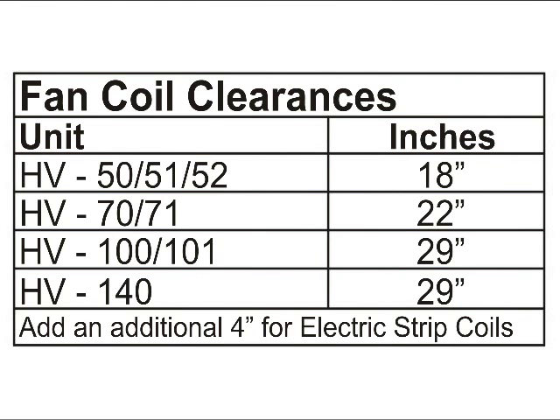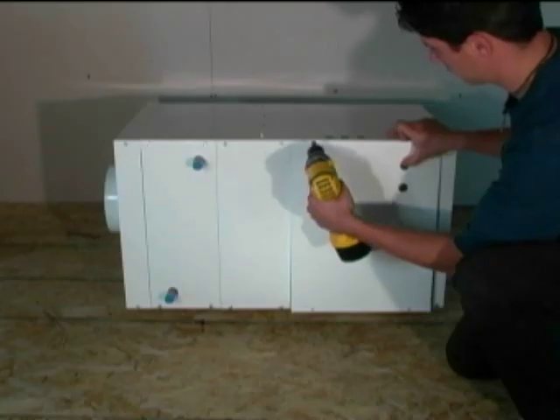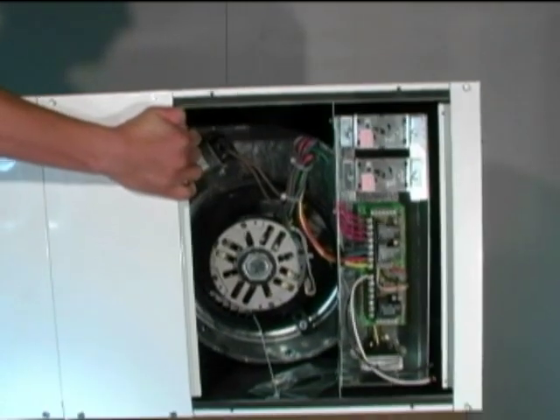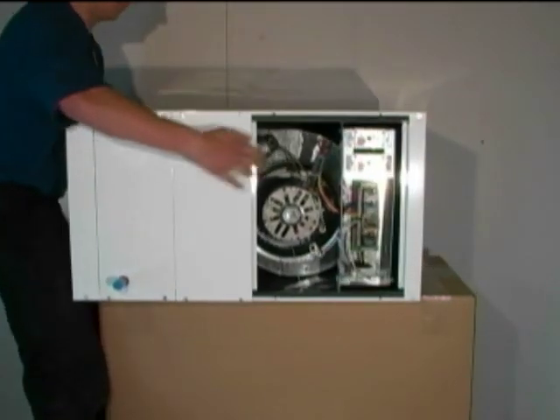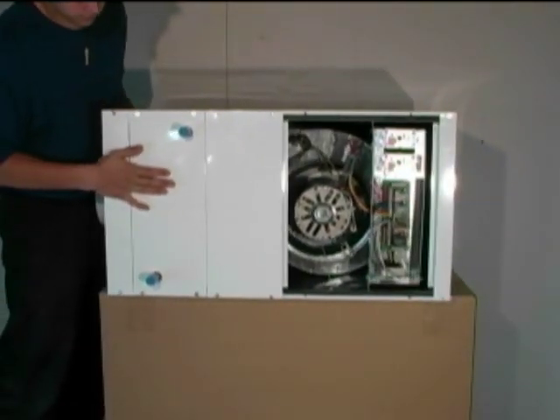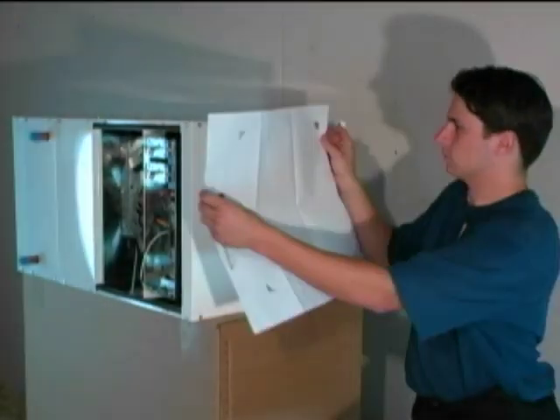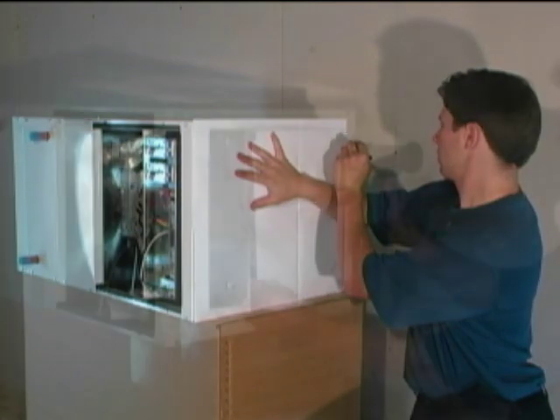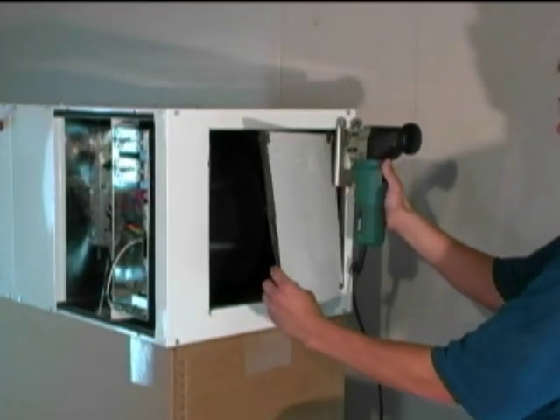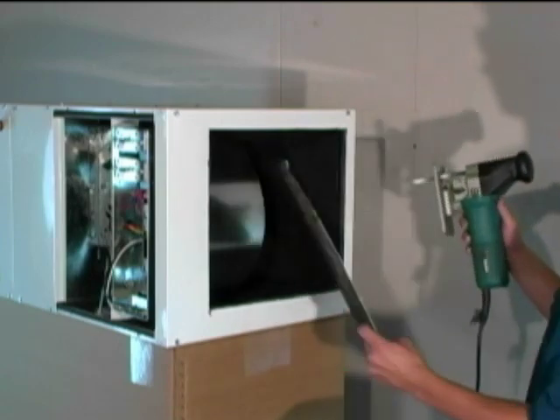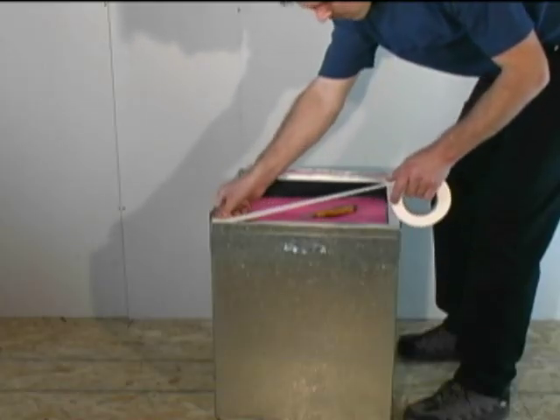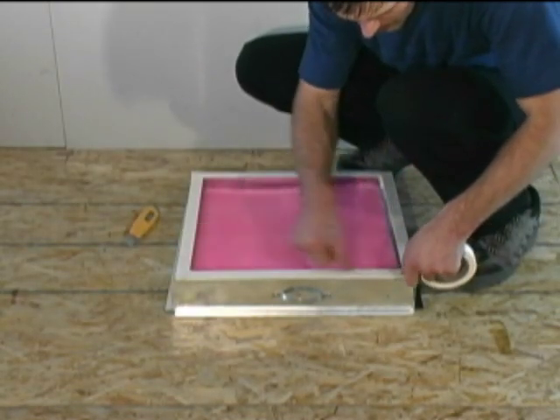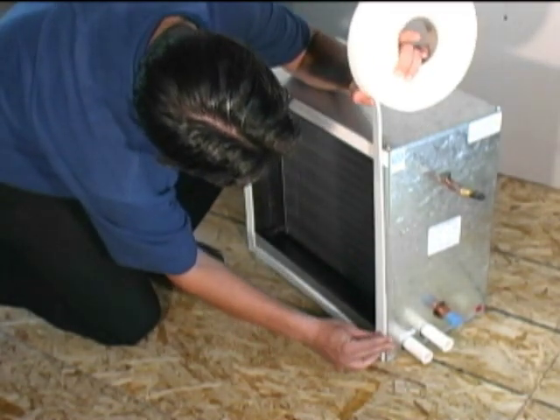Refer to the installation guide for clearances on the model being installed. For easier maneuvering, remove the front access panel. Because the unit is designed for various installation positions, it's necessary to cut a hole in the unit before attaching the return air. Locate the top of the unit, and then use the provided return air template to mark the return air opening. Cut the hole, being careful to cut completely through the sound-absorbing lining. Depending on the configuration of the unit, apply double-sided isolation tape to the return air base, filter rack, or cooling coil to create an airtight seal.